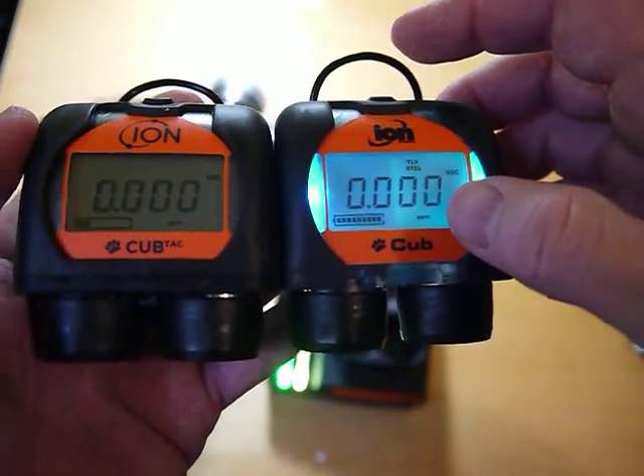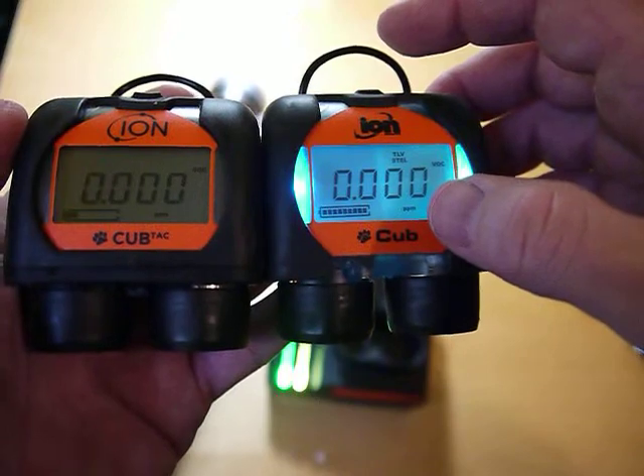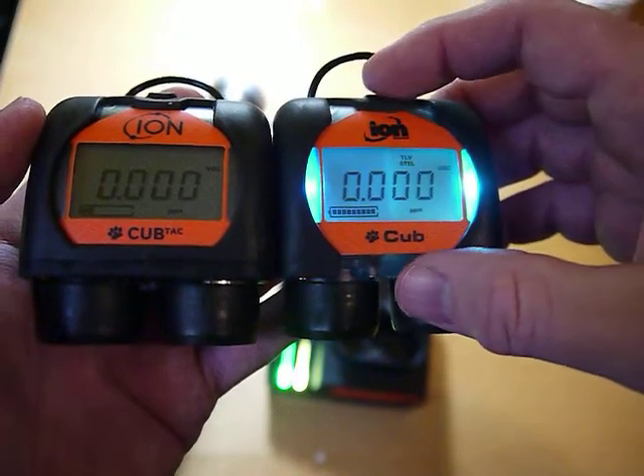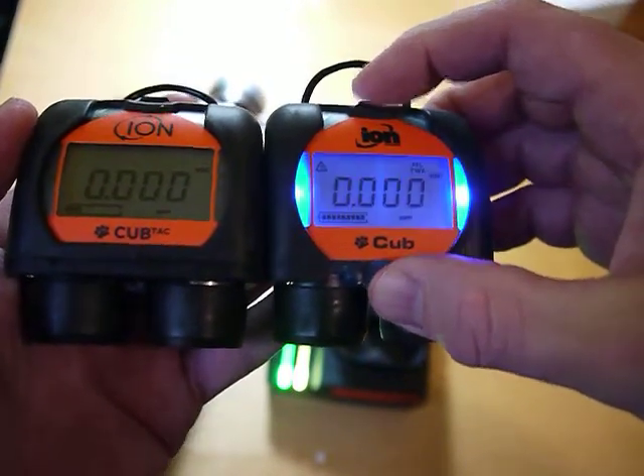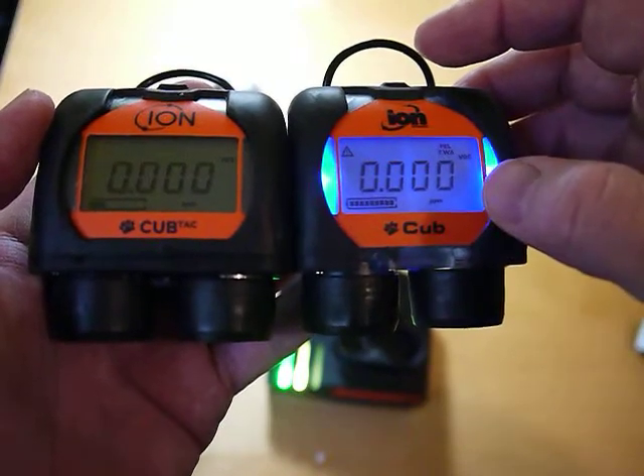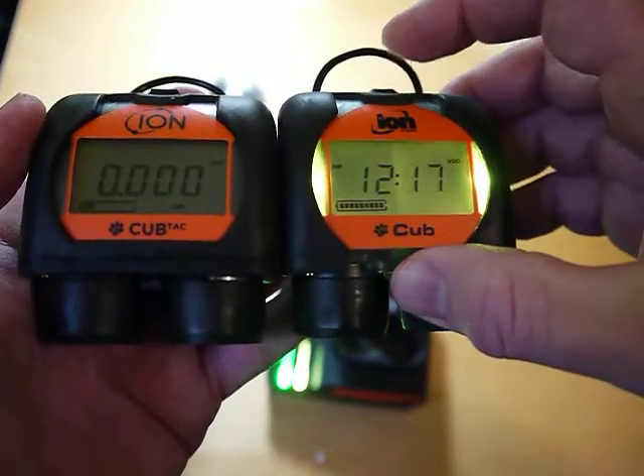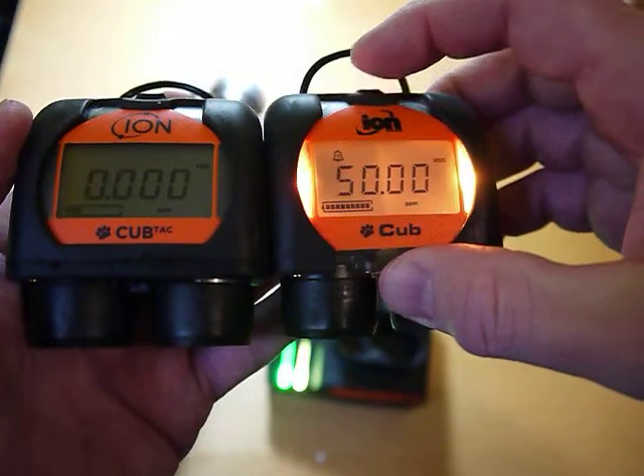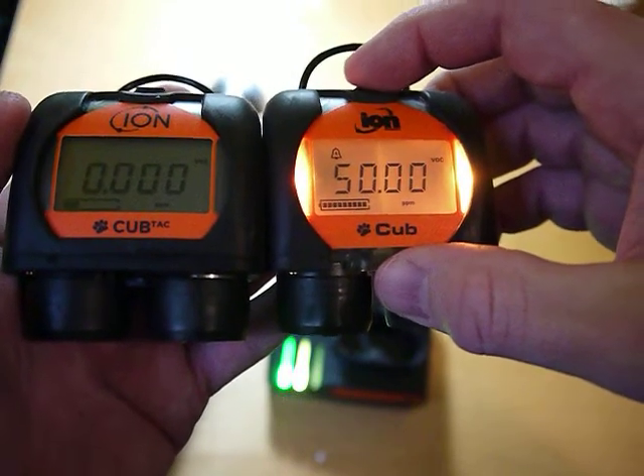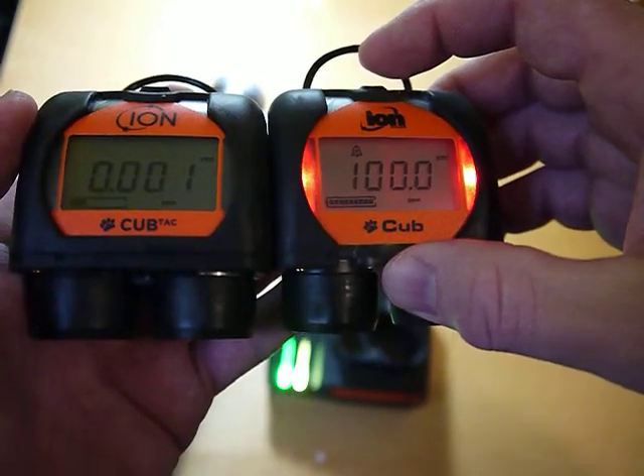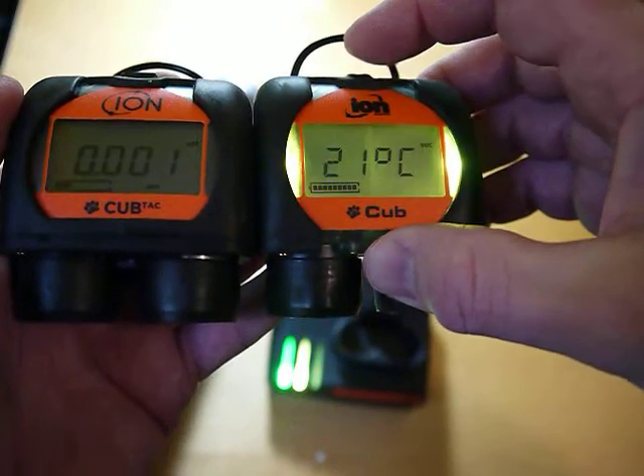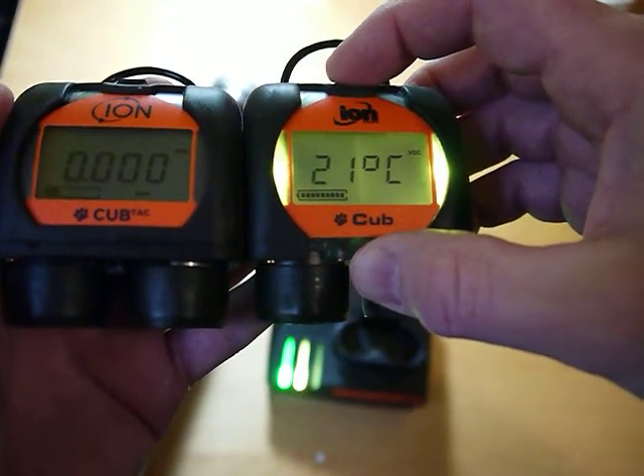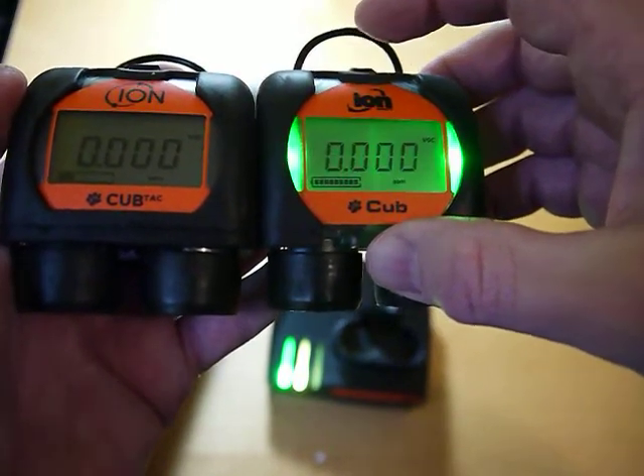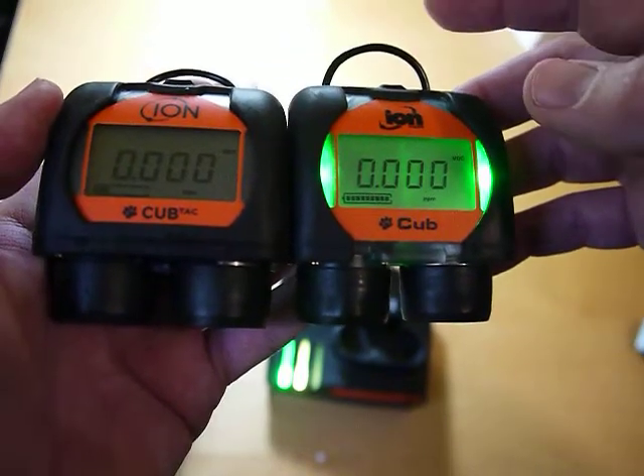This is showing the TWA, the STEL 15-minute average calculated value. This is the TWA 8-hour average. I've got the time, the low alarm, and the high alarm, the temperature, and if I had turned it on, the next screen would be the ability to manually calibrate in the field without the dock.